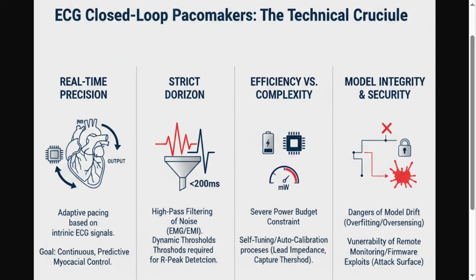That slow reaction time, high latency, leads to undersensing, or worse, delivery of a pulse during the heart's natural refractory period, which can be catastrophic. The signal processing pipeline is brutal. Raw EGM acquisition, filtering, baseline wander removal, R-peak detection, morphology classification, and then the pacing decision logic, all running on a few milliwatts. If the filter is too complex, it increases latency and drains the battery. If it's too simple, you're oversensing elevator noise.